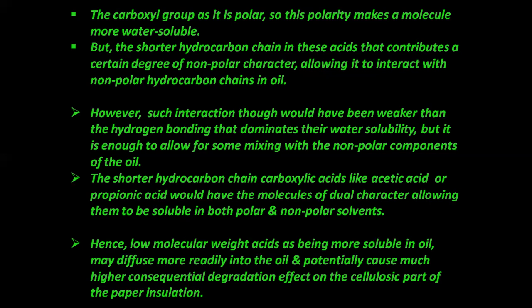Hence, low molecular weight acids, being more soluble in oil, may diffuse more readily into the oil and potentially cause a much higher consequential degradation effect on the cellulosic part of the paper insulation.